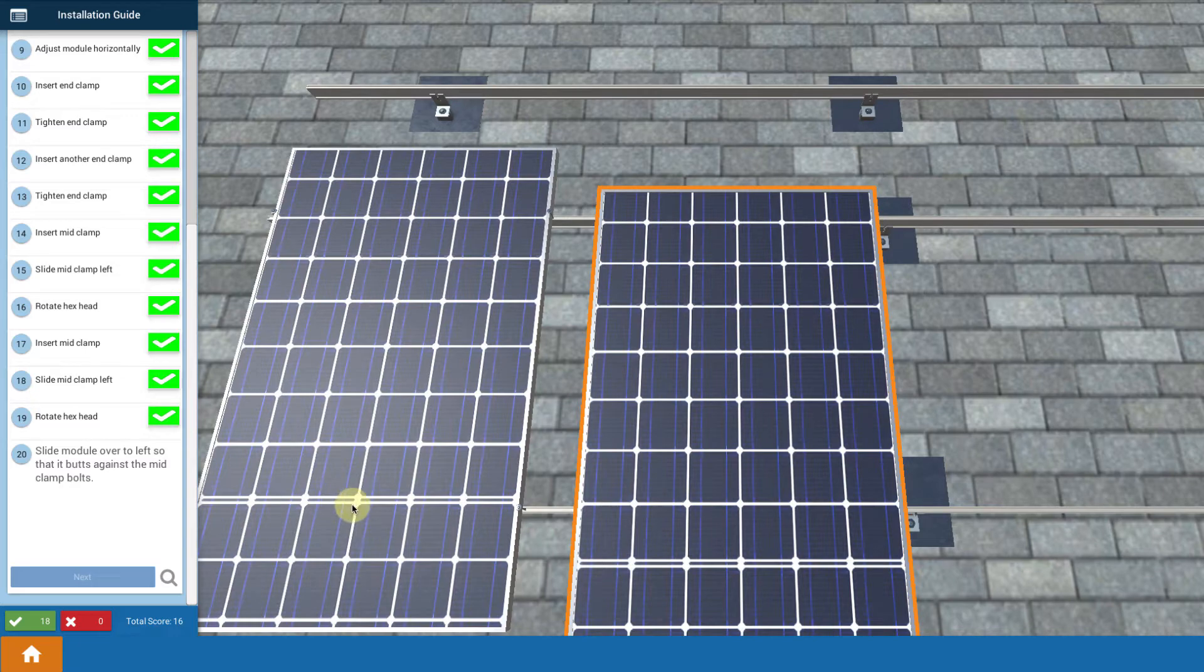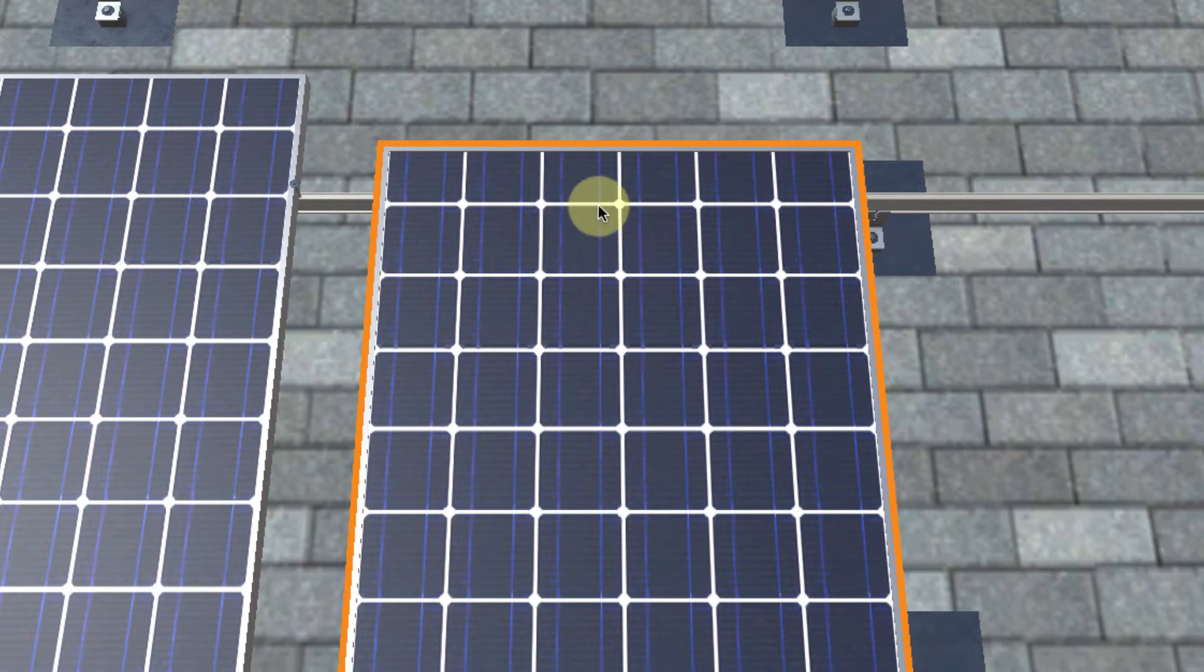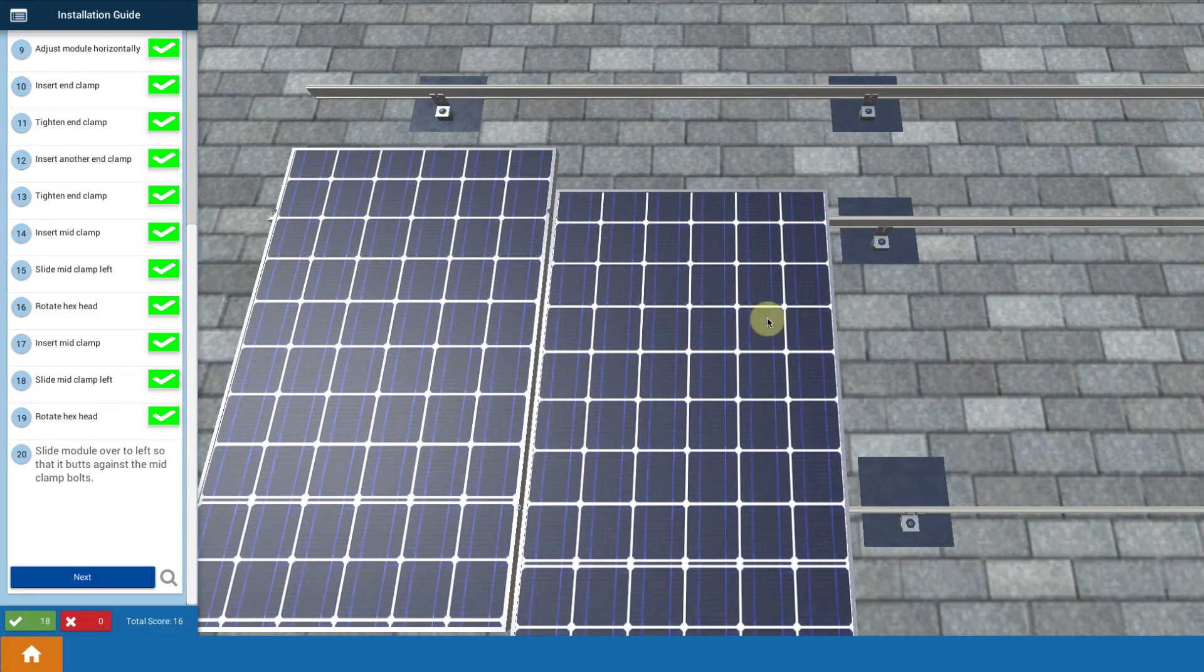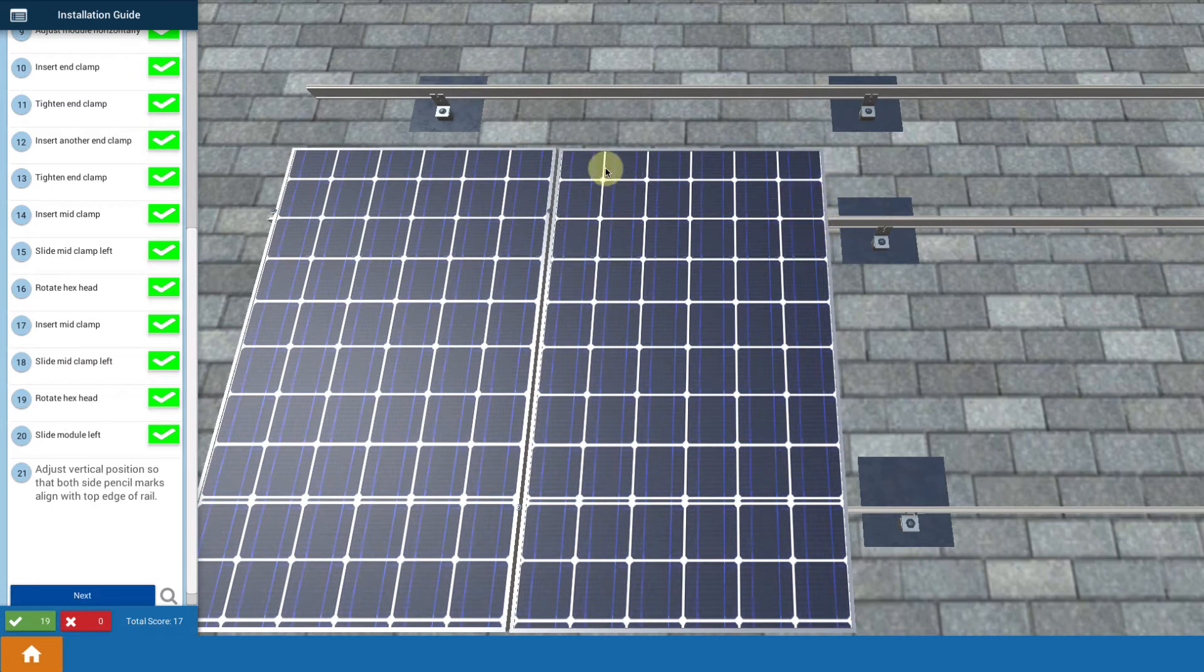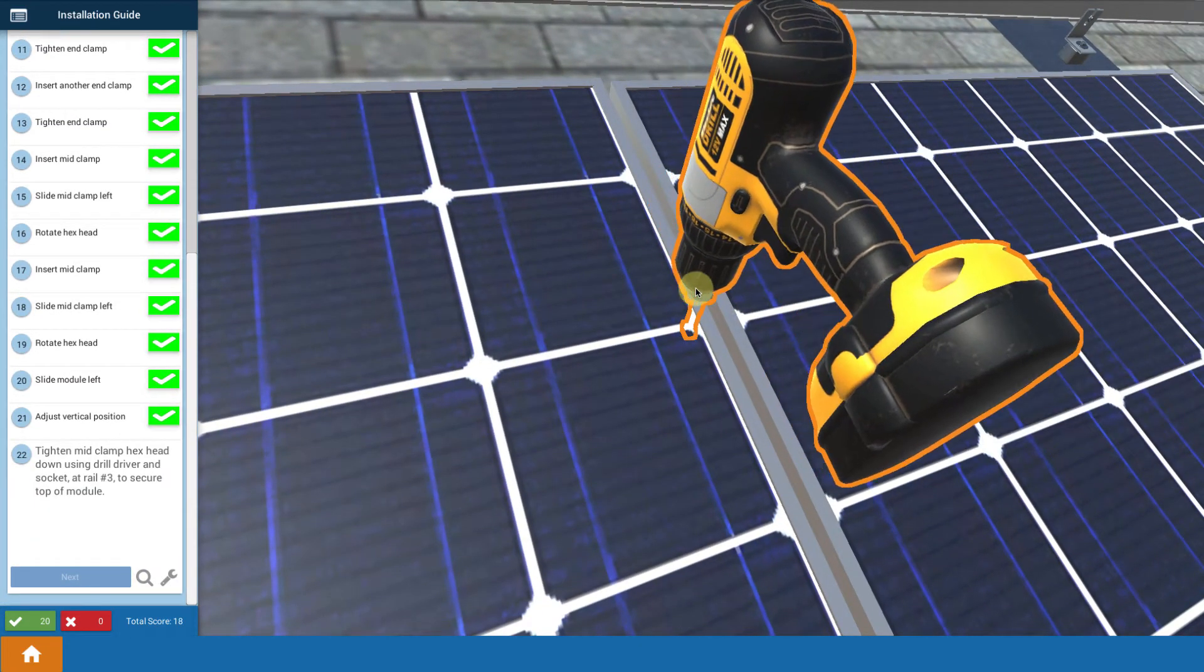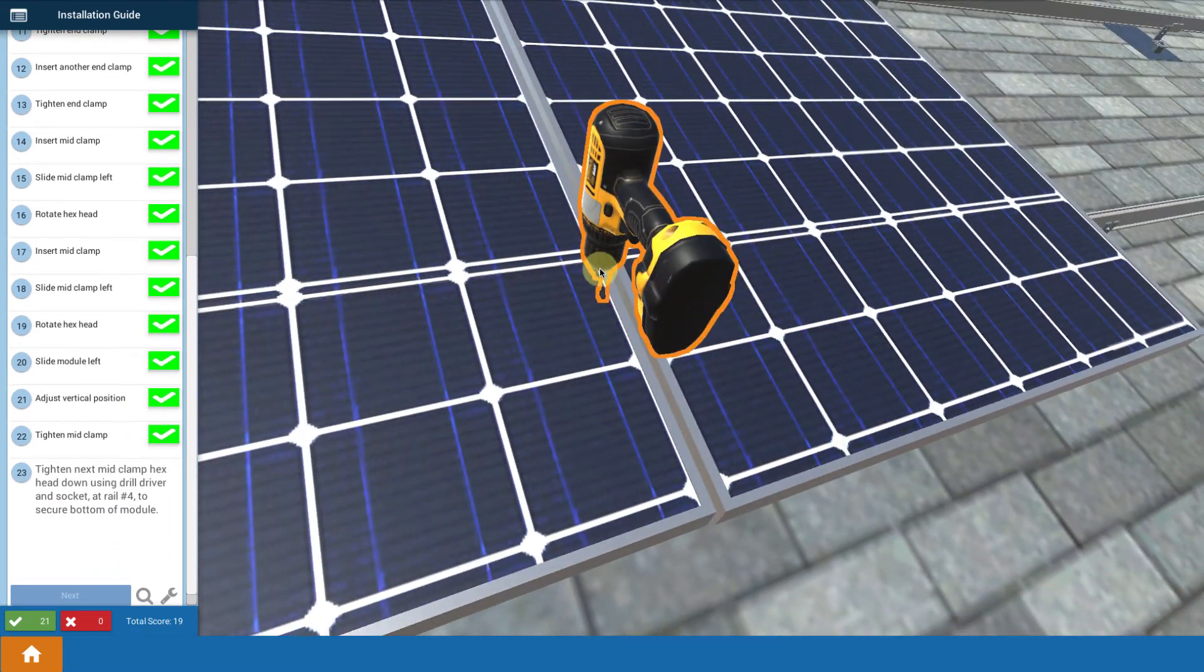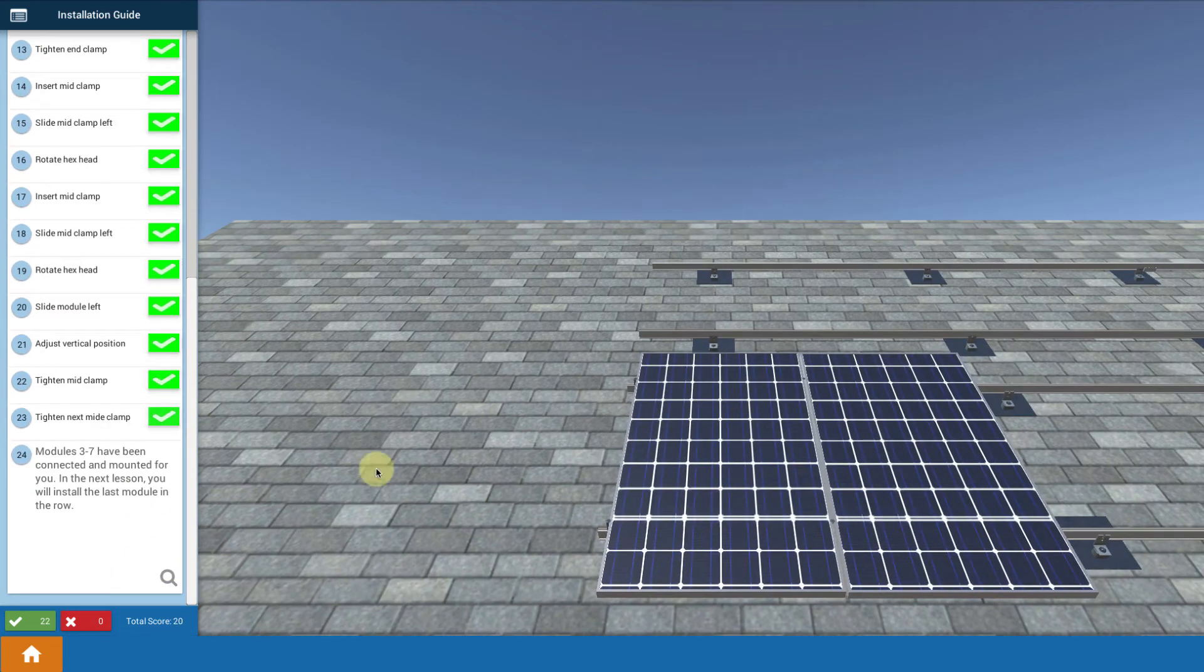And so we do that. We bring up the next module. Now we've laid it down for you. But here again, you would have that curled up wiring underneath that would be laying on top of your optimizer. But you want to make sure when you lay it down that there's no pinching going on. That's the critical thing going on here. You do not want to pinch those wires because that could lead to a ground fault. So now you want to slide the module over so that it fits right next to those bolts that you put in. And then you're going to slide it up and you're going to align it with that 12 inch mark. And that's going to align your modules to the rail and to each other. And then you're going to come along with your tool here and you're going to tighten it using that and down below as well. So now I've tightened it up.